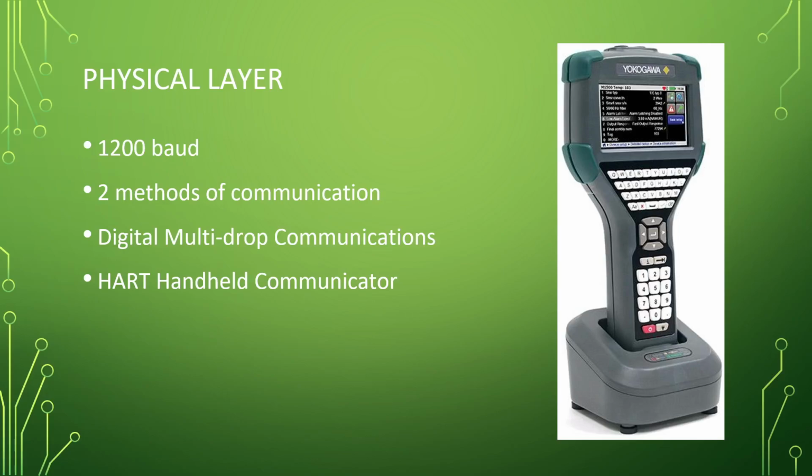All right. So, yep, we could do analog or the frequency shift keying for our communications. This is a 1200 baud rate. All right. So, something to be aware of. Max drop is up to 15 devices. I don't know if the video said that. I don't remember. 15 devices is what we can have on this at once.